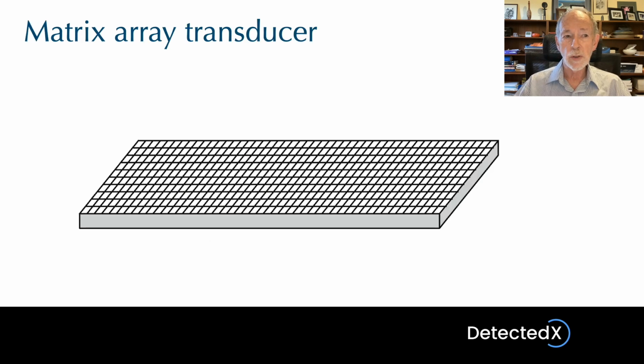Now we have a somewhat different transducer. This has been sliced across the width, but also along the length, and so there's now a very large number of elements. Now these transducers are referred to as matrix array transducers, and these do exist. They are commercially available. They're still relatively expensive at this time, but presumably once manufacturing issues have been sorted out, they will become much more widely used and perhaps will eventually become the standard kind of transducer.